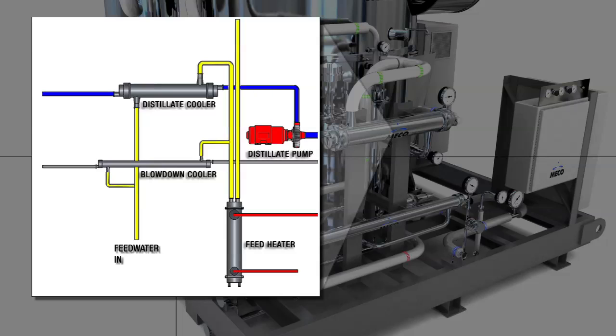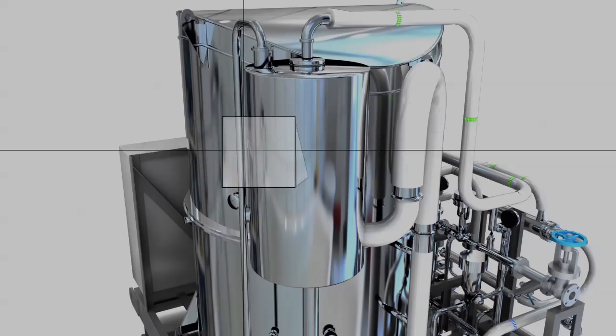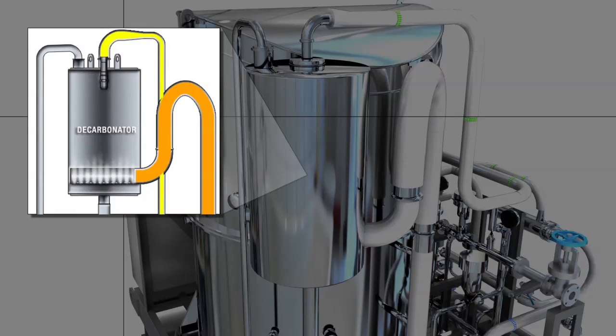This efficient heat exchange in the coolers minimizes the system's energy consumption by reducing demand on the feed heater. The preheated feed water flows to the decarbonator and is sprayed through rising vent vapor which strips non-condensables from the feed water before entering the evaporator.